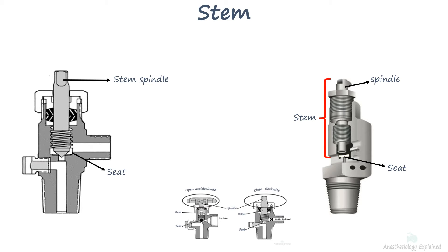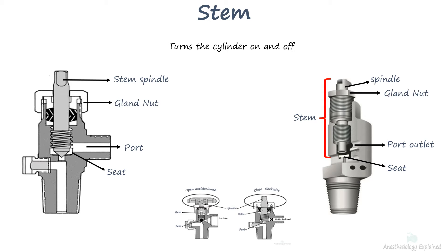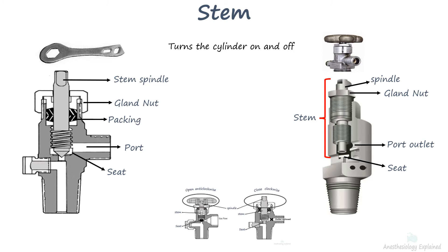Each valve has a stem, which is in close proximity to the seat. Together, they function as a door to the port, enabling the cylinder to be turned on and off. To ensure a reliable seal, the gland nut is meticulously tightened to compress the packing against the spindle. The stem can be manipulated for on/off control using its spindle, where either a hand wheel or a wrench can be employed.